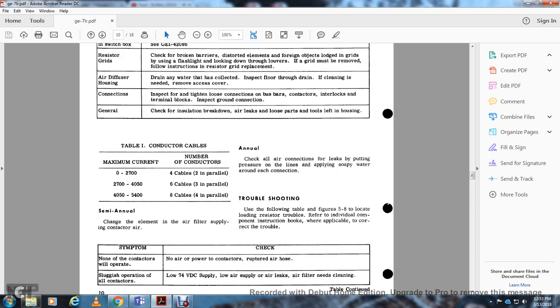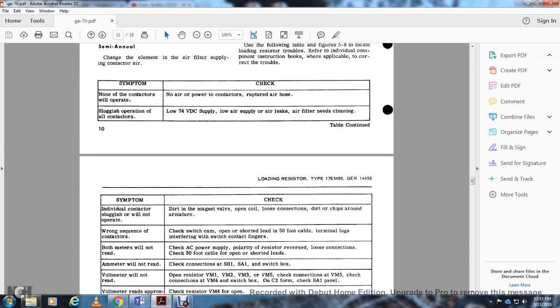Symptom: none of the contactors will operate. Cause: no air or power to contactors, ruptured air hose. Sluggish operation of all contactors: low 74 volt DC, low air supply with air leaks, and air filter needing cleaning. Individual contactor sluggish, will not operate: dirt with the magnet valve open, cleaning, open coil, loose connections, dirt chips around the armature. Wrong sequence of the contactors: check the switch cam, open shorted lead for the 50-foot cable, terminal lugs interfering with the switch contact fingers.